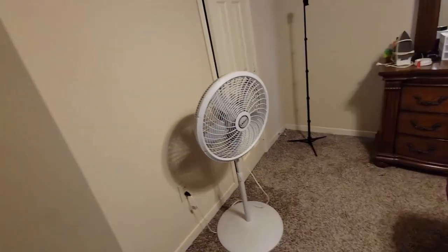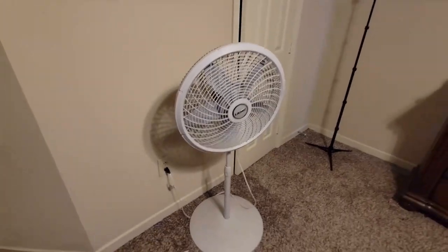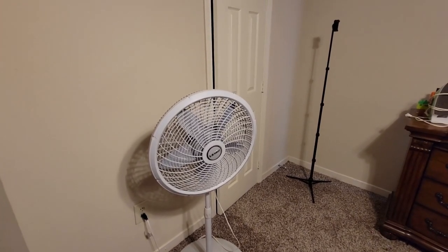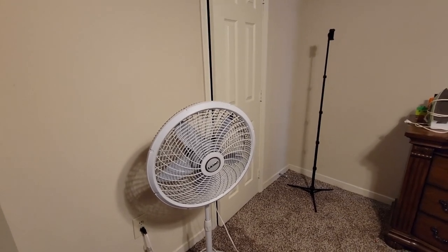While we're looking at this fan, this is one point you need to keep in mind: no fans can actually be on when you're hooking up to your dialysis machine. It has to have still air, because you don't want any dust kicking around that could cause an infection.